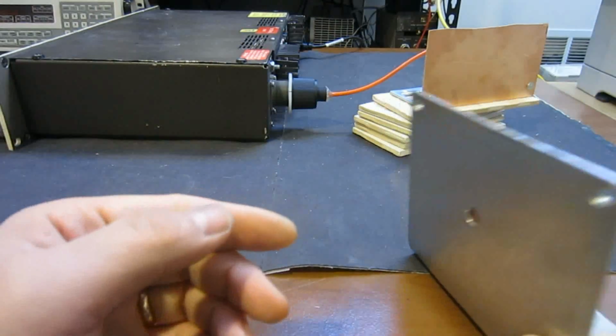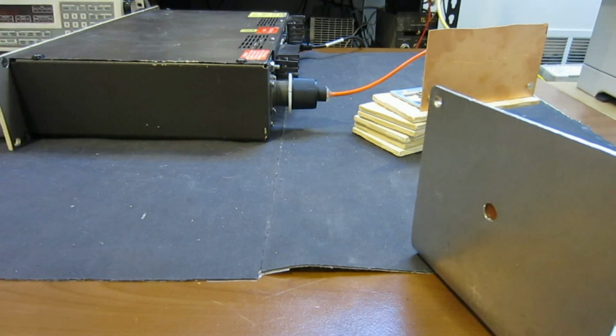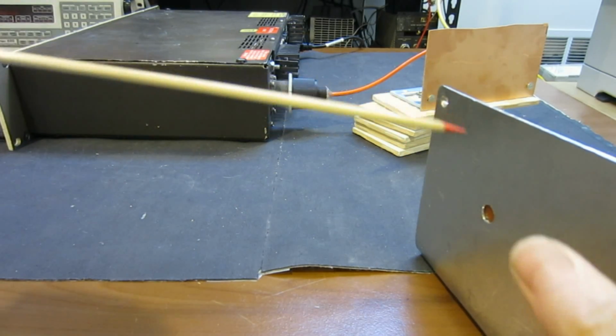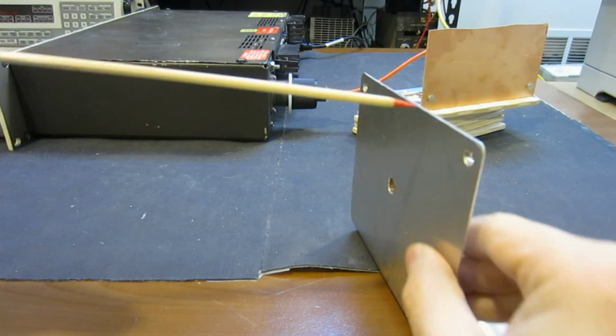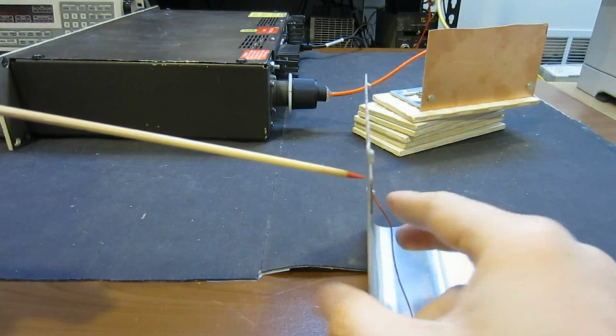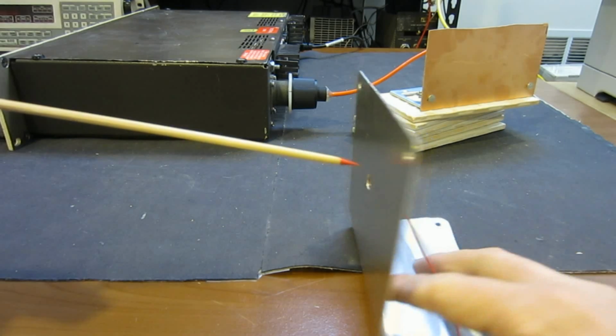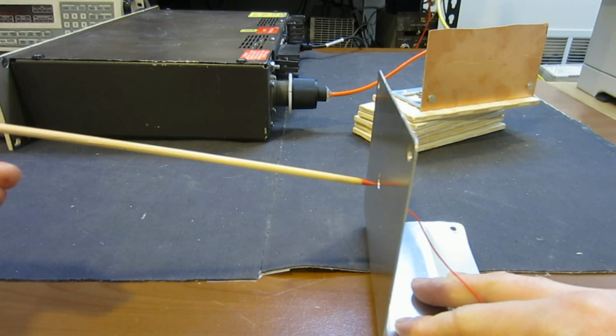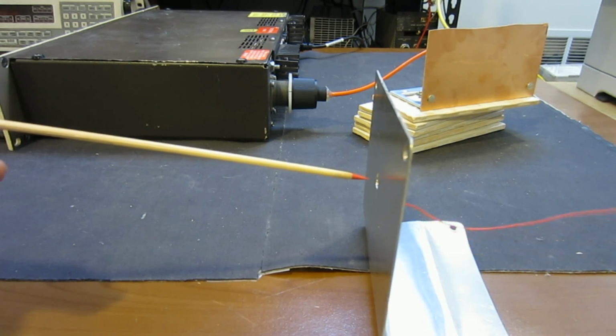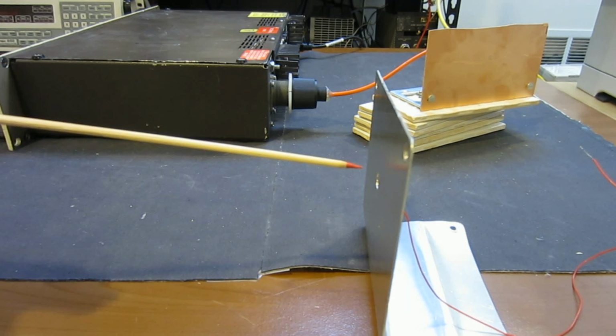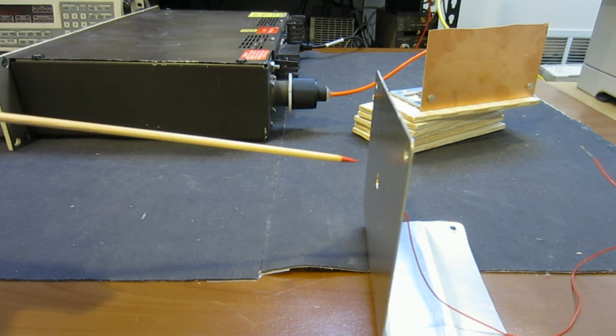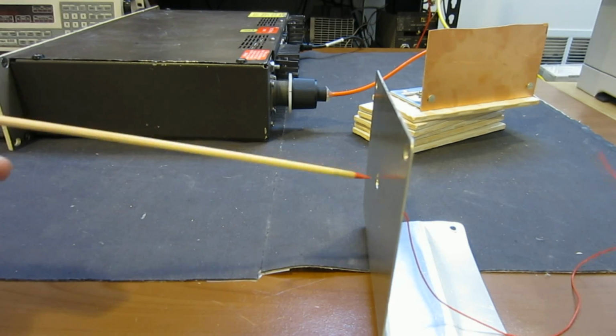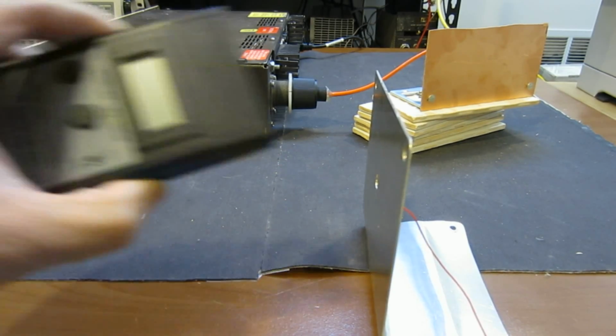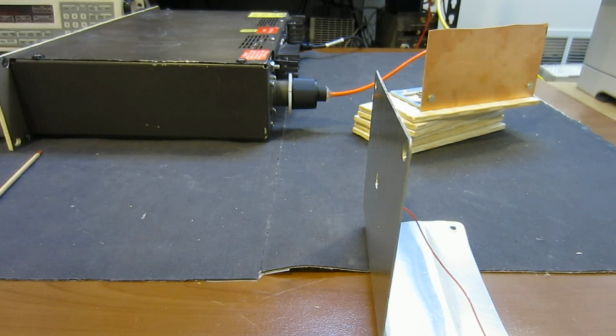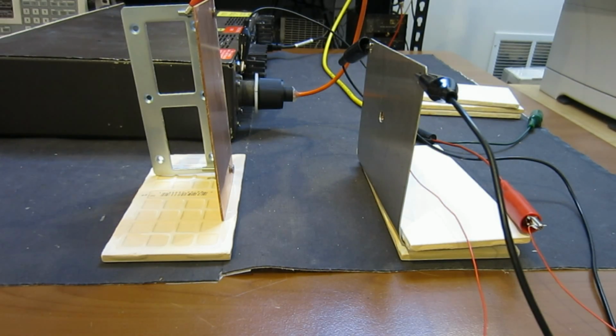So basically, the idea is when this is placed into a field, with the aluminum case grounded, this would induce a voltage on the capacitor here. So by measuring the voltage induced here, we can determine what voltage is applied in the field. So that's the same idea as what I just showed you from this field meter.